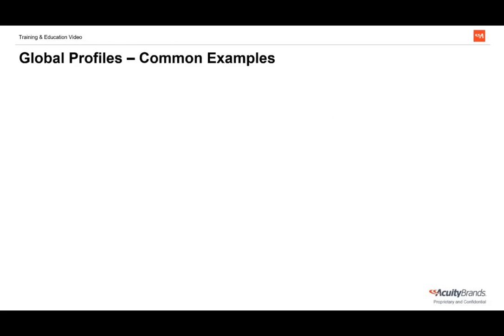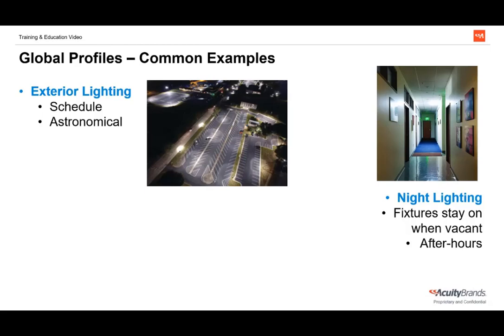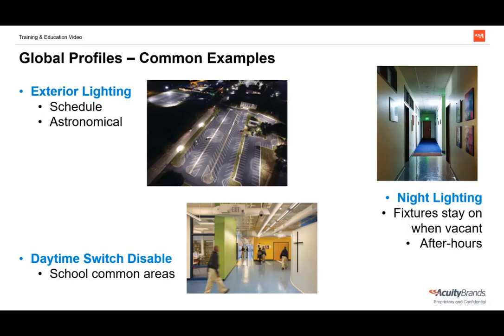Here are some common examples used in nLight control systems, sometimes required by code. Exterior lighting utilizes a time of day or astronomical schedule — sunrise and sunset — and location information is critical for accurate times. Night lighting, or egress, tells specific lights to remain on even when the area is vacant, usually only after hours. A daytime switch disable profile disables switches in common areas of schools or retail spaces during normal operating hours, preventing people from turning the lights off.